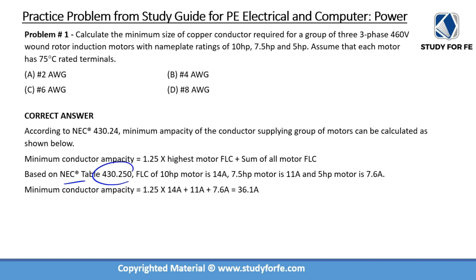We have three-phase motors, which are covered in table 430.250, and FLCs can be extracted from there. The FLC of the 10 horsepower motor is 14 amps, the 7.5 horsepower motor is 11 amps, and the 5 horsepower motor is 7.6 amps. I would recommend you go to the table and verify these values for yourself.